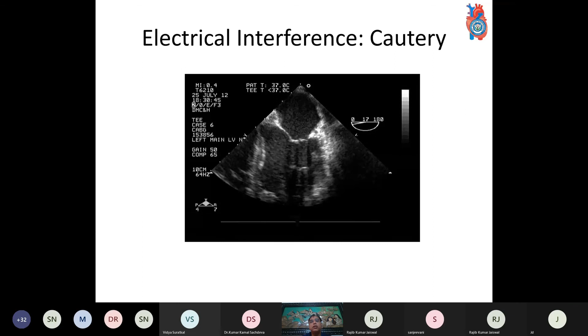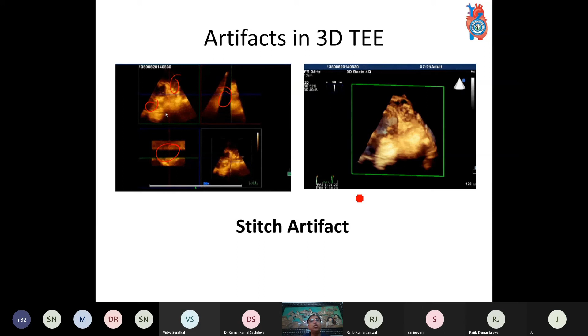There are certain 3D artifacts, because in three dimensions the transducer has to do such a laborious job. It has to throw so much ultrasound in three-dimensional ways and receive it back, and sometimes when the received waves are not properly stitched, there are gaps. Like if you see, there are gaps in between. These gaps are called a stitch artifact. The computer has to stitch all these ultrasounds coming back from the structure and make a proper display on the screen, and this causes a defect in the image. With the improvement in the hardware of ultrasound machines, more and more stitch artifacts have been resolved now. But still, if you're taking too much tissue in a single beam, the artifacts would be there.